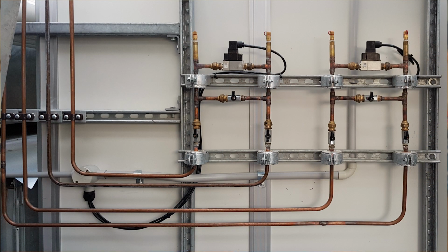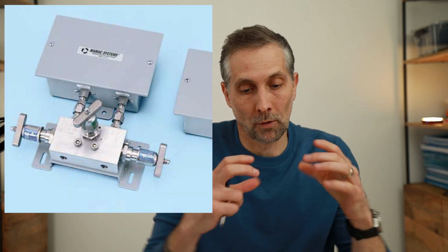Now, the first thing we're going to talk about is a manifold. All system pressure transmitters, in my opinion, should be provided with a manifold, which is basically an arrangement of 3 little mechanical or manual isolation valves that are provided by the mechanical contractor. Sometimes they are individual little valves: an isolation valve for the supply, an isolation valve for the return, and a little bypass isolation valve. But sometimes you can purchase them pre-arranged on a little plate, with the supply isolation, the return isolation, and a little bypass, that you just install and connect everything up to.